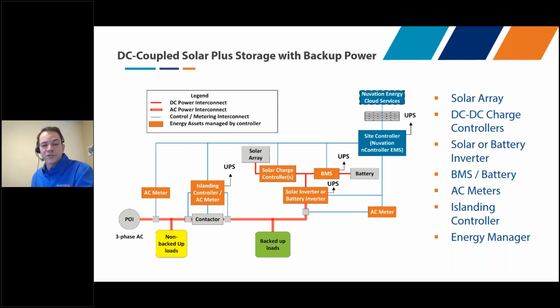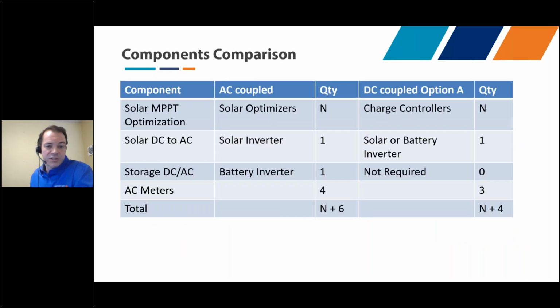So there's just a single solar inverter or battery inverter doing that DC-AC conversion. To roll that up into a component comparison, we do that on the next slide. This shows a table of the components involved in AC coupled versus DC coupled. As highlighted at the start, one advantage of a DC coupled system is it has fewer total components. For solar optimizers and charge controllers, let's say we have N number of those depending on the size of the solar array. In both cases we have solar DC to AC, but the storage DC to AC is only required on the AC coupled side, not for DC coupled. DC coupled also saves an additional AC meter. So the net of that is an AC coupled solution is N plus 6 in terms of components, whereas a DC coupled is less, at N plus 4. So there are fewer components in the system, which can contribute to reducing overall system cost.